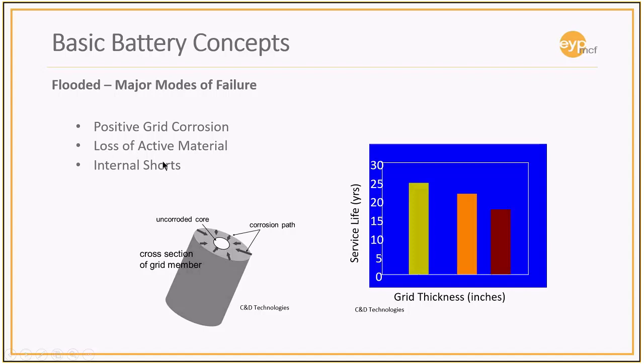This material can potentially reduce the capacity of each of the cells in the battery. So loss of the active material due to this shedding, and then internal shorts when that material falls to the bottom. And over time, the jelly jar cells or the flooded cells are typically a 20-year battery, or they're talked about as a 20-year battery. There are other configurations that can go longer, but typically the service life and the grid thickness are where you're going to see these things change.